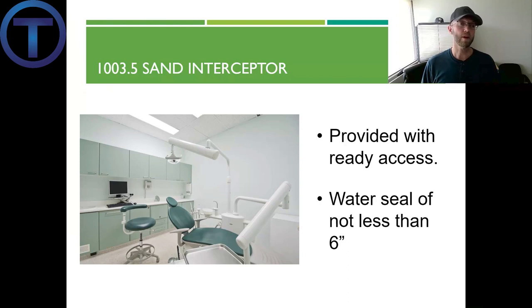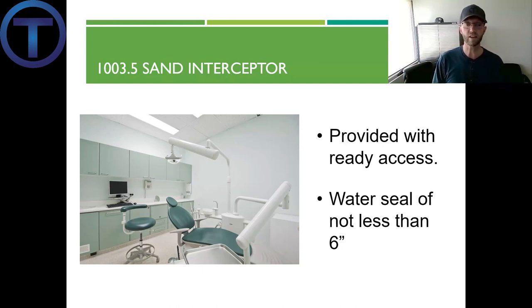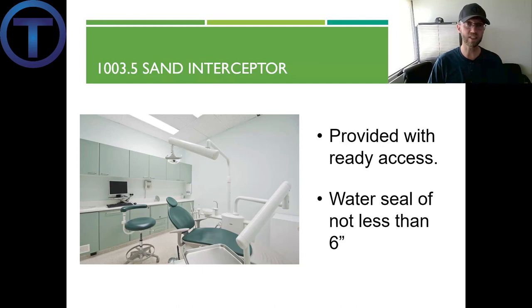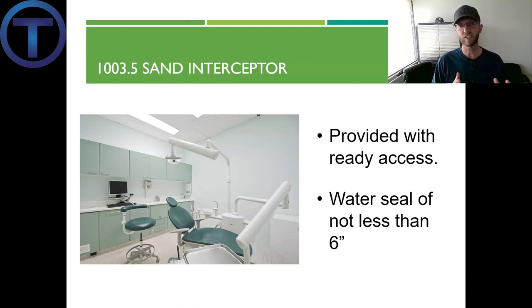Section 1003.5 talks about sand interceptors. They need to be provided with ready access and have a water seal of not less than six inches. Where would you need a sand interceptor? One example is a dental office — if they're doing any grinding of teeth, they may have a sink with a lot of sediment that can clog the drains, so there's a unique trap under there just to catch that ground sediment. Another example may be a jewelry shop or a place that polishes rocks.